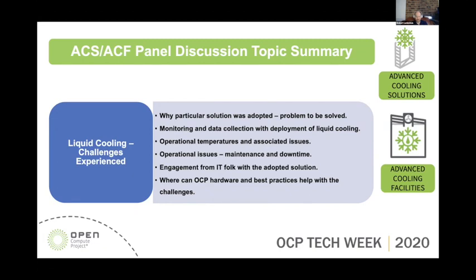There's still demand for a lot of air-cooled systems, so as we develop liquid-cooled systems, we're trying to develop something that can serve a dual purpose. If we have an air-cooled system, we'd design it so it could be retrofitted or converted to liquid cooling, using common designs, then upgrade to processors or other things that have liquid cooling requirements. So there's still a lot of mixed requirements coming from both air cooling and liquid cooling as we adopt and delve more into liquid cooling.